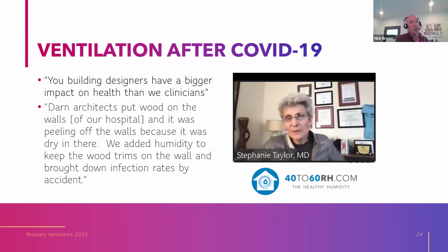In one of the hospitals she was working in, they had wood paneling. "Darn architects put wood on the walls of our hospital, and it was peeling off the walls because it was so dry in there. We added humidity to keep the wood trims on the wall, and we're shocked to find infection rates went down as a result by accident." This is why she advocates for this range, 40 to 60% relative humidity, as the sweet spot, where certain things that happen when the air is really dry don't happen, and certain things that happen when the air is really moist don't happen. So good rule of thumb. And of course, ventilation plays a big role in that.